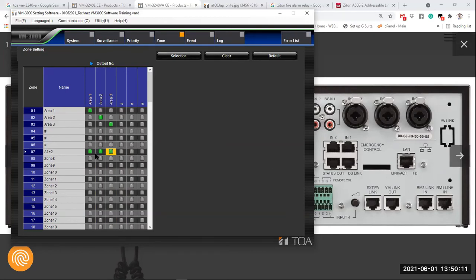If I am sitting at the reception, looking for somebody who must be either in production or in dispatch, instead of calling production and then calling dispatch, I just create a single button where I can call those 2 areas at once. So this is where we create zone 01 to zone 89. And this is why we have zone 90, which is an all call zone.